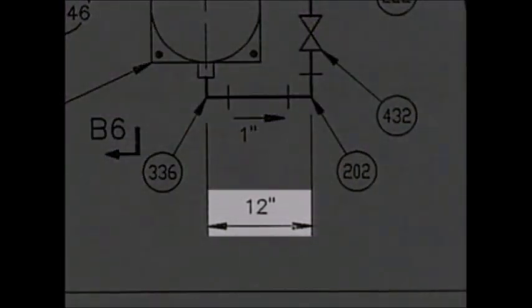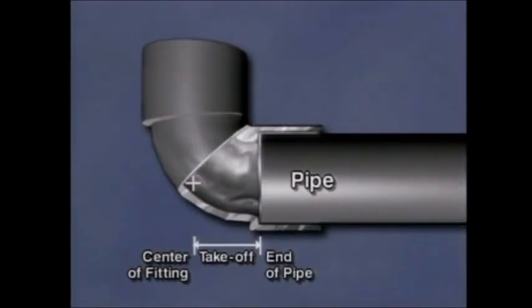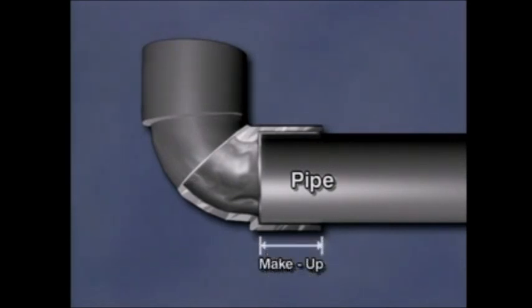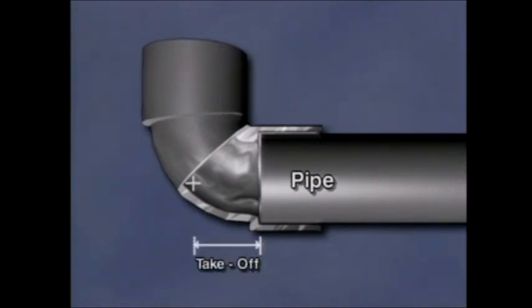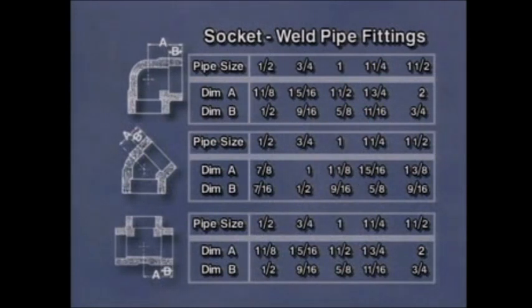Most measurements are center to center — that is, from the center of one fitting to the center of another fitting. This is not the length of the pipe. The pipe ends are not at the center of the fitting. With screwed, socket weld, and plastic fittings, the pipe ends insert a certain distance into the fitting — this is called make-up. The distance from the made-up end of the pipe to the center of the fitting is called the fitting takeoff. To determine the actual pipe length from a center-to-center measurement, you must subtract the takeoff for each fitting. Takeoff dimensions vary with pipe size, and tables giving takeoff dimensions for each size pipe can be found in pipe manuals.